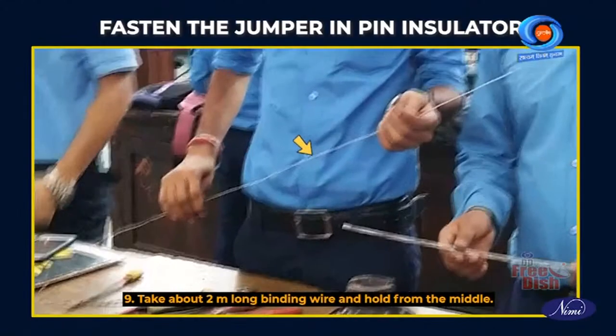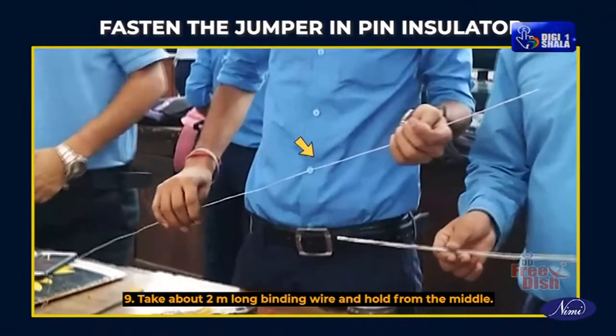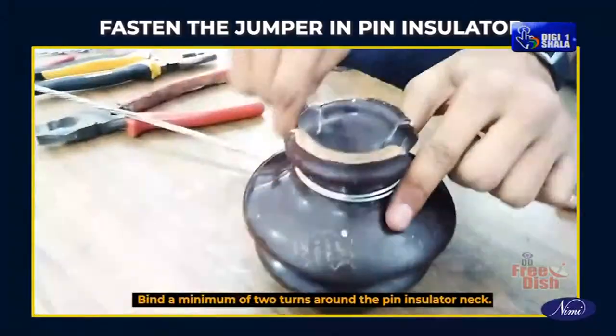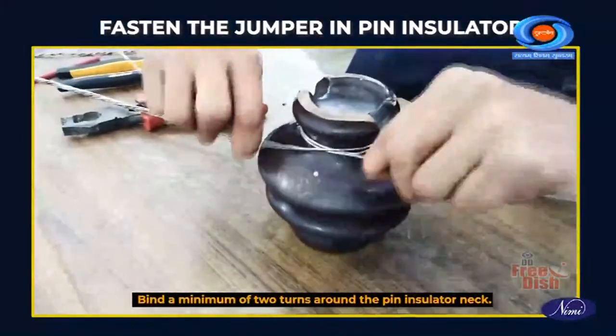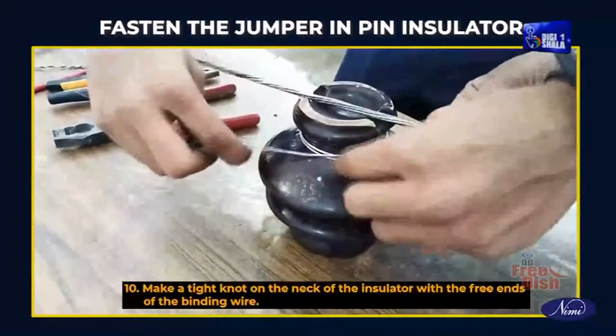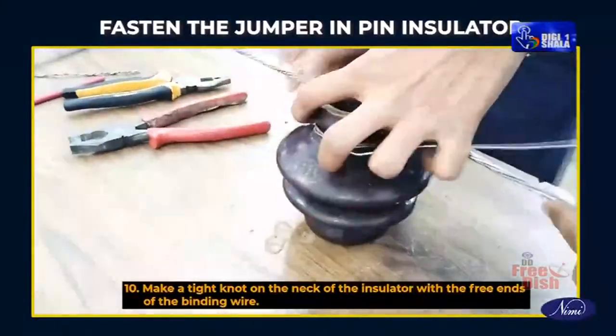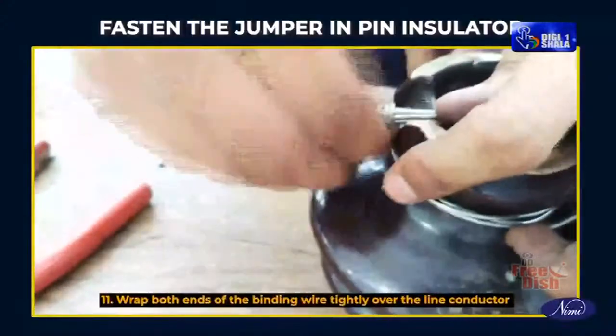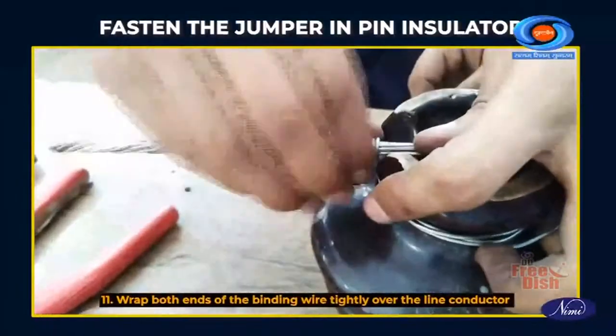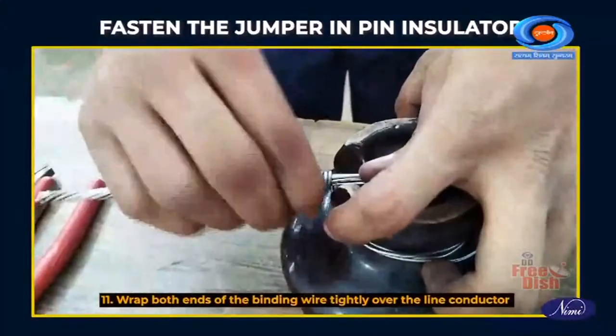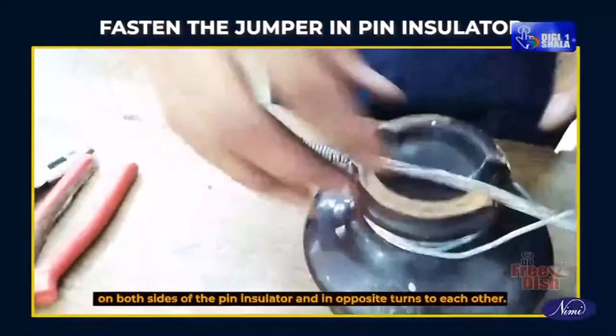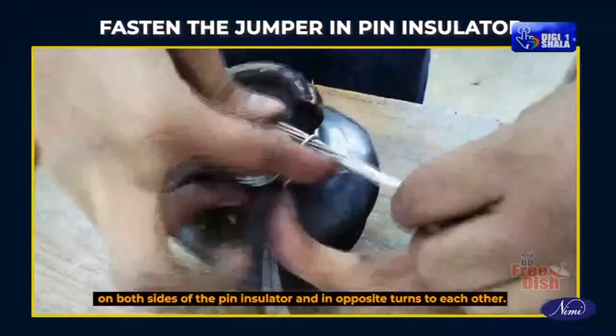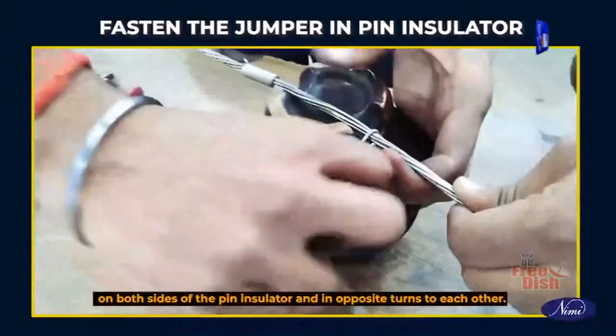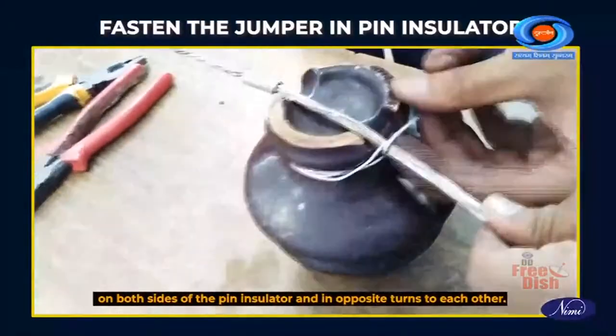Take about 2 meter long binding wire and hold from the middle. Bind a minimum of 2 turns around the pin insulator neck. Make a tight knot on the neck of the insulator with the free ends of the binding wire. Wrap both ends of the binding wire tightly over the line conductor on both sides of the pin insulator and in opposite turns to each other.